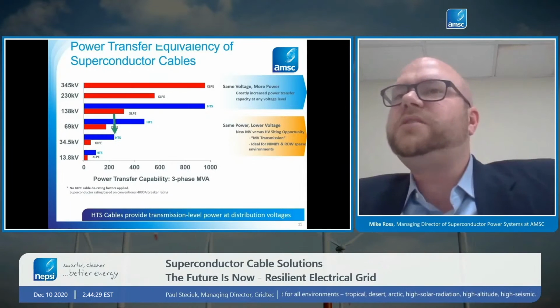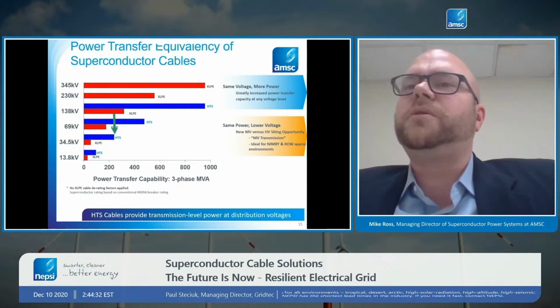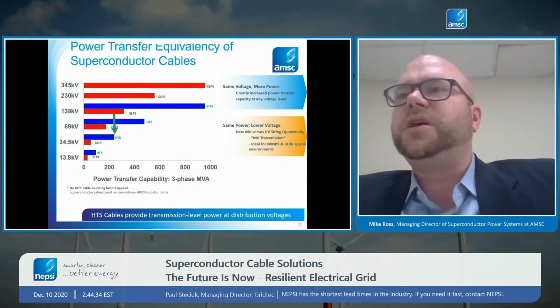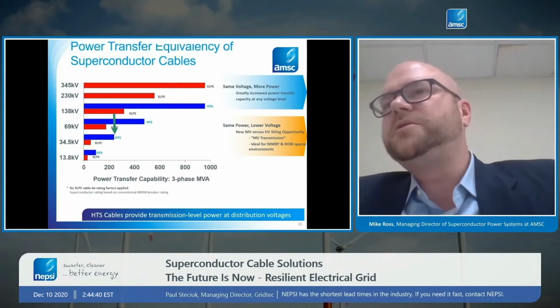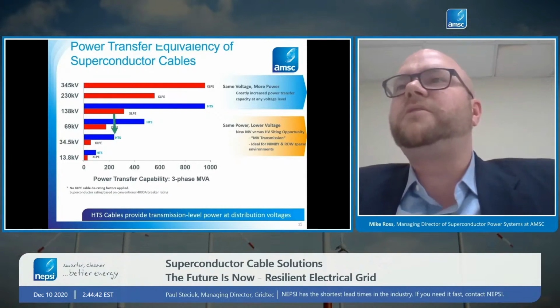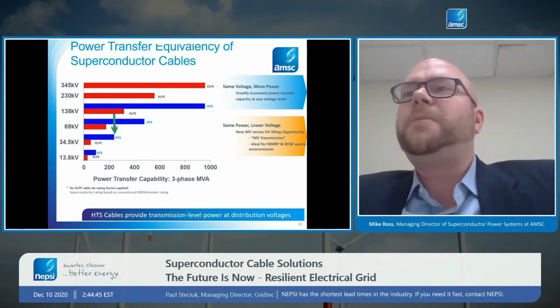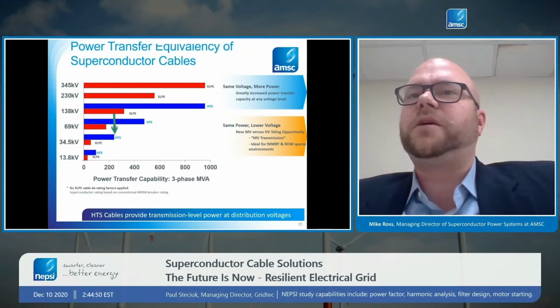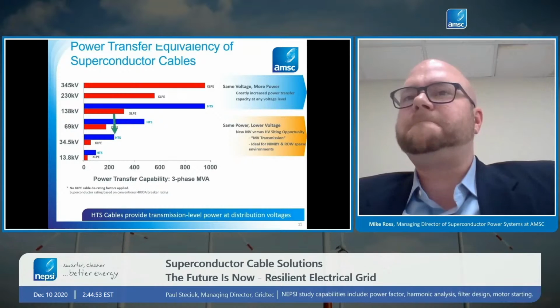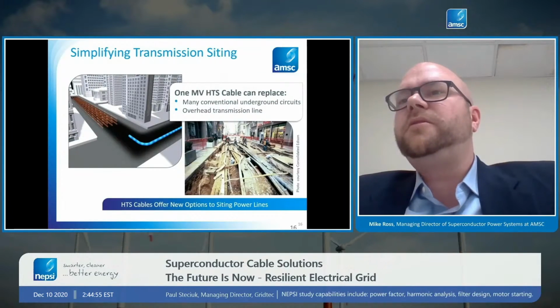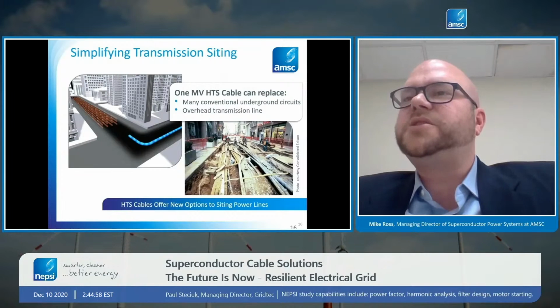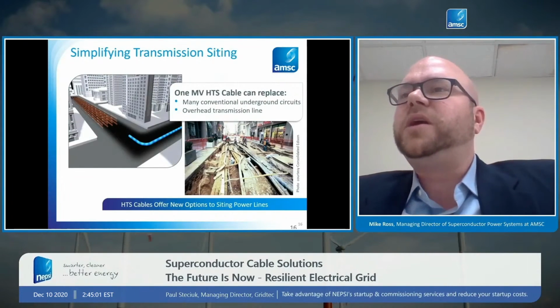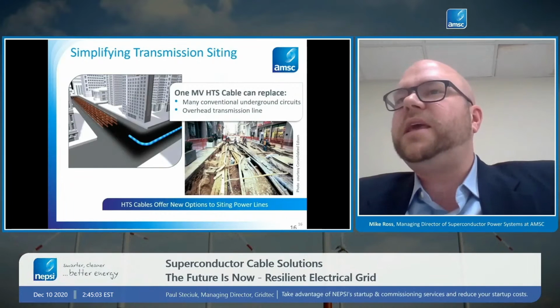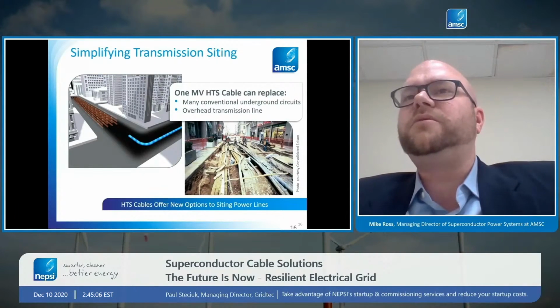And this is where we really see major value for especially urban utilities. If they could move bulk power around their grids at distribution voltages, there's a tremendous amount of value that can be saved by not having to install large, expensive transmission equipment in urban areas. So we'll talk more about that. Also, the siting advantages of the technology. We talked about this a lot already. We can put them deep underground. They don't generate heat. A lot of things that you can't do with conventional cables.